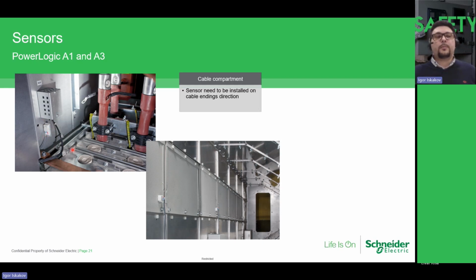Of course, you should check your local safety regulations. If the cable endings are too near to the installation zone, of course, it will be dangerous for the personnel. But in very old switchgears, you have cable endings quite far away from the door. So it's even possible to install them while in use. Of course, you should check regulations. For example, in Finland, the regulations mean that if the distance is more than 30 centimeters, you can install the arc flash protection, but the person who does the installation must also be supervised.